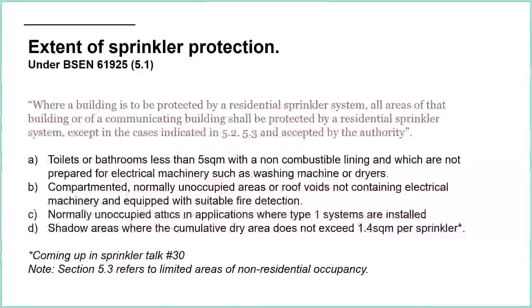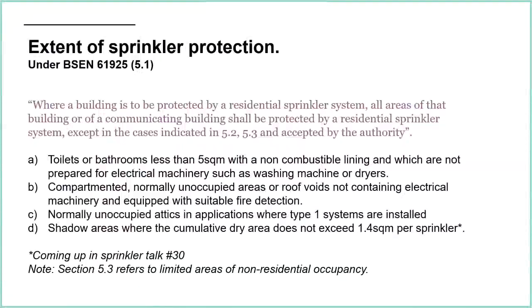Compartmented, normally unoccupied areas or roof voids are also excluded, provided they don't contain electrical machinery and are equipped with suitable fire detection. They've gone into a little more detail with these areas, saying they have to be compartmented and have suitable fire detection within them. Normally unoccupied attics are excluded only where type one systems are installed, making a distinction between different kinds of applications.